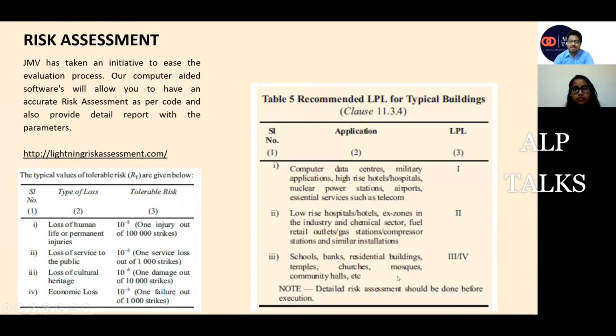How can we decide whether it is level 1, level 2 or another level based on history, or for a particular area? For risk assessment, there is a standard for the calculations, and as per that there are multiple values, so when we do the calculations at different levels, the values are different. First of all, we check at level 4 because it is the least prone to lightning. If my building comes out protected at level 4, then we select level 4 and do the designing at level 4. If it is not protected, then we proceed to level 3, and accordingly level 2 and level 1. In this way, we decide the level of protection.